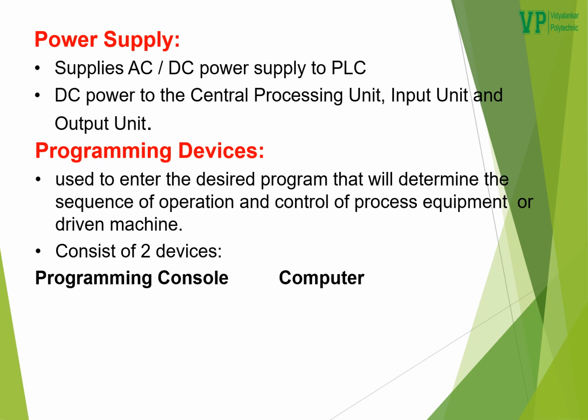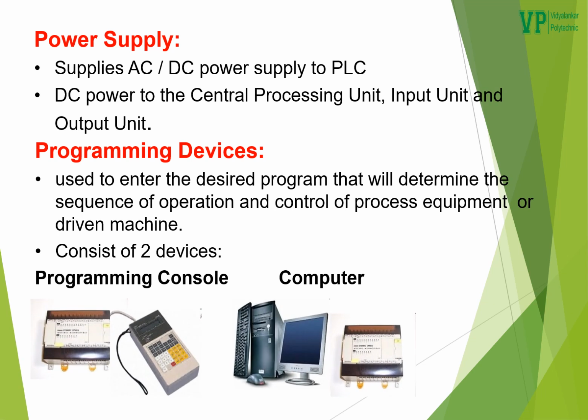Programming devices. They are used to enter a desired program that will determine the sequence of operation and control of process equipment or driven machines. There are two types of devices, programming console and computer. Well, it means these are the devices which are used to feed the user program to the PLC. It could either be done through the programming console as it appears to be in picture, or it could be done using a personal computer or a laptop.